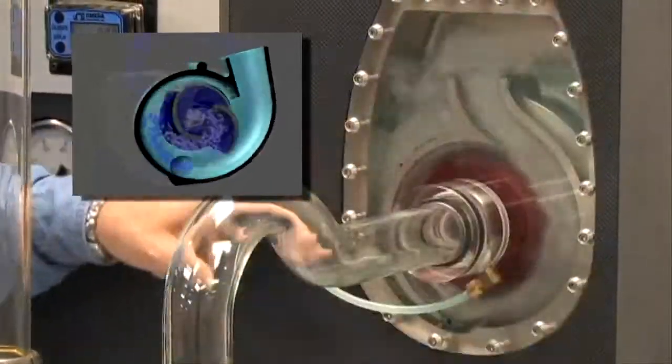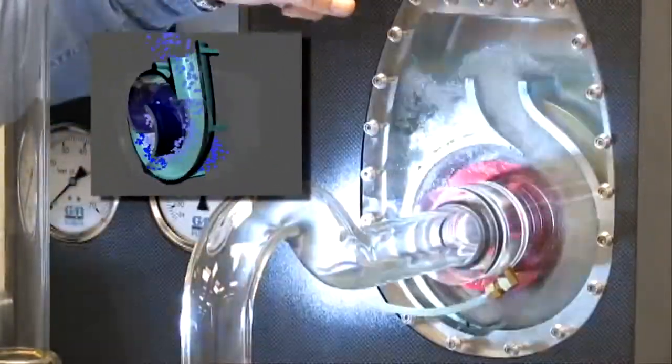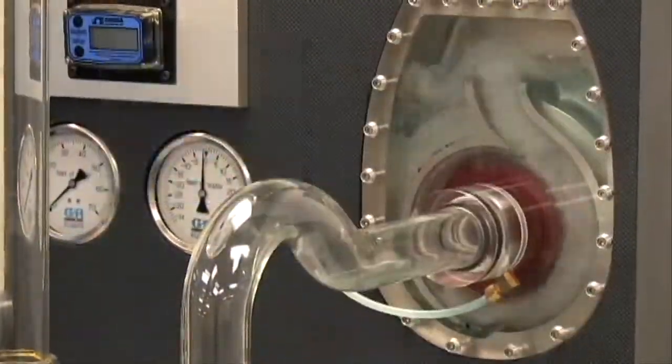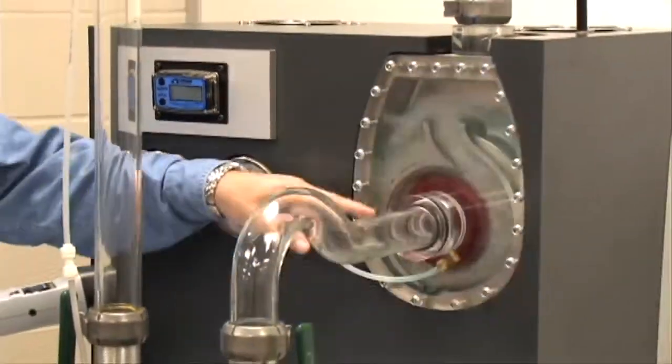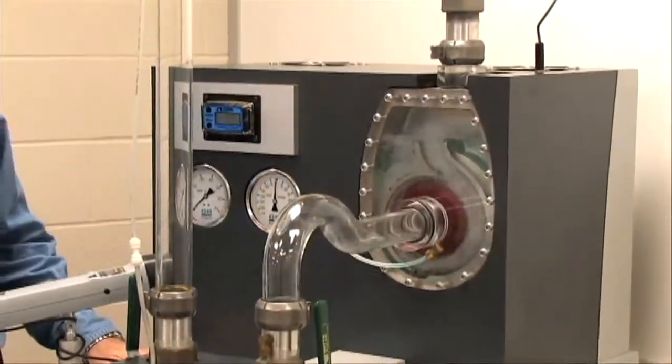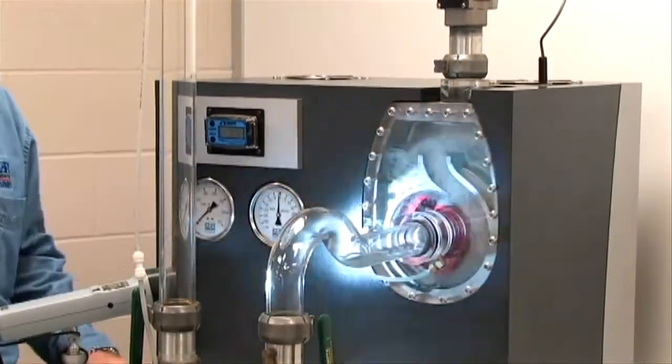The heavy water falls back down through a recirculation port and the air then is evacuated through an open-ended line or through an air release device. All the while that we recirculate the water inside the casing and remove the air from the top, we create a low pressure at the eye of this impeller.